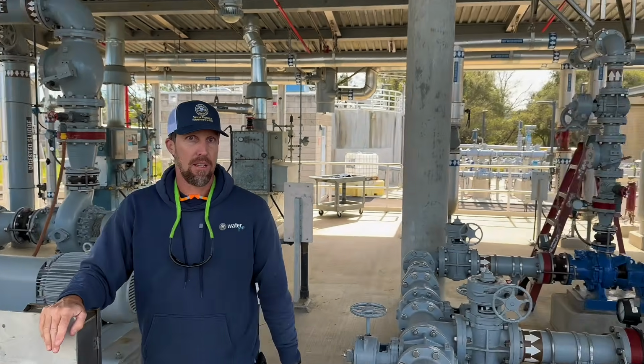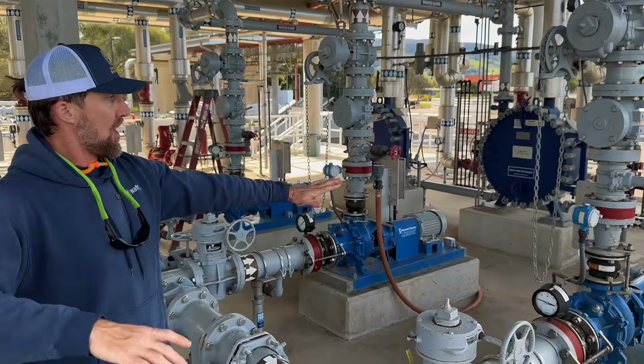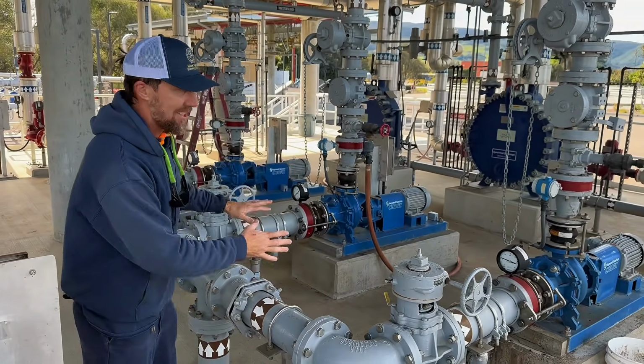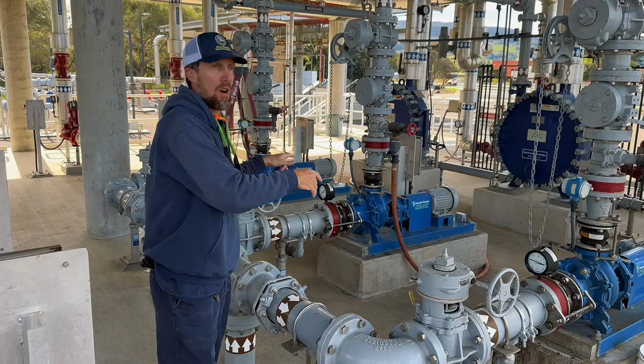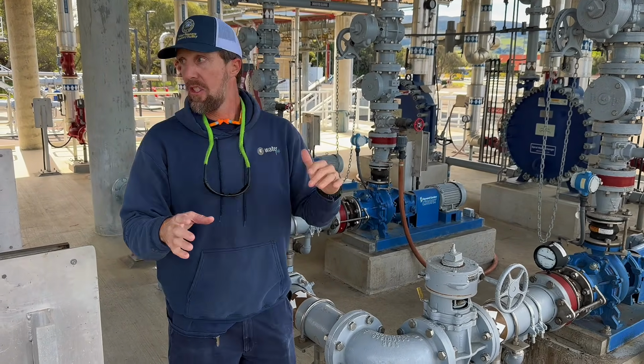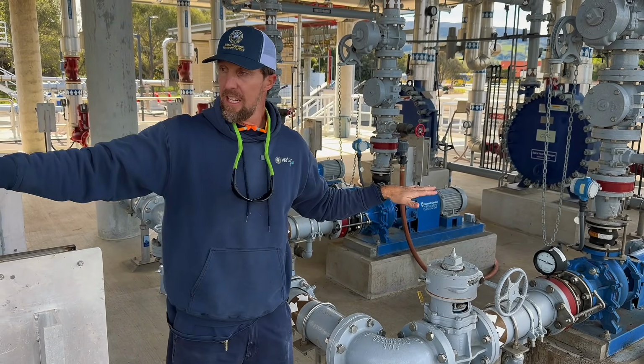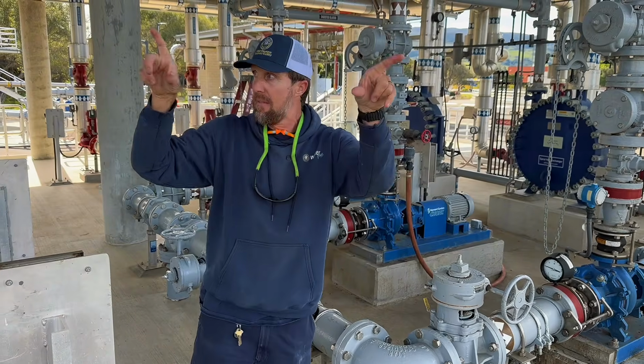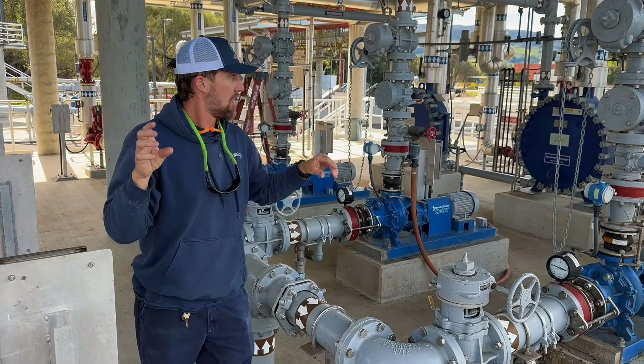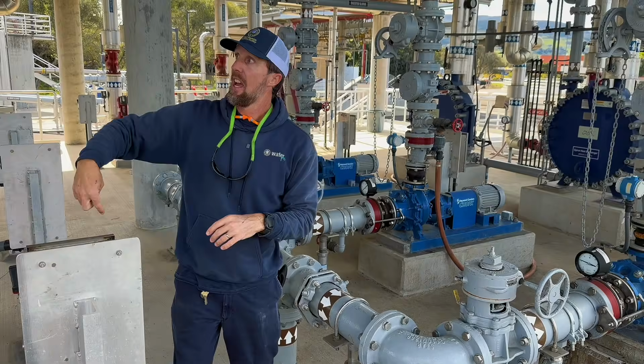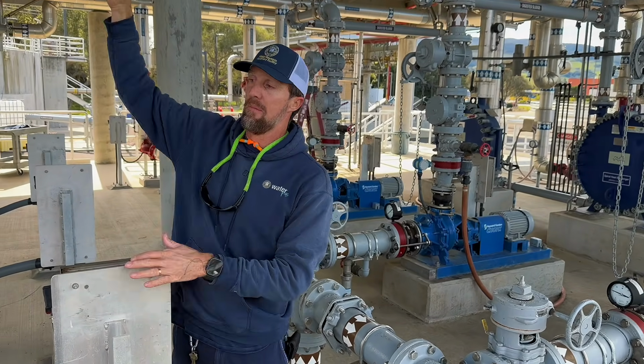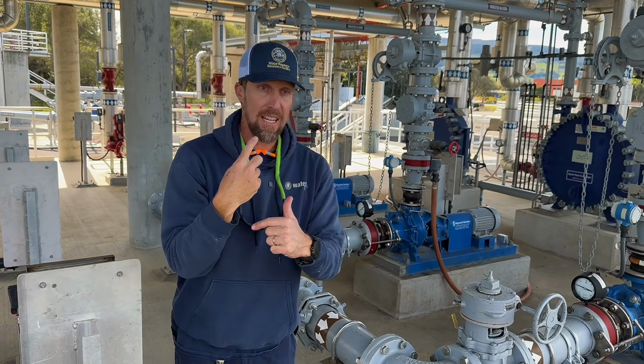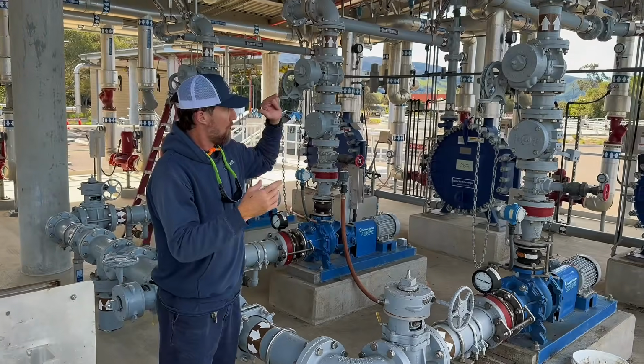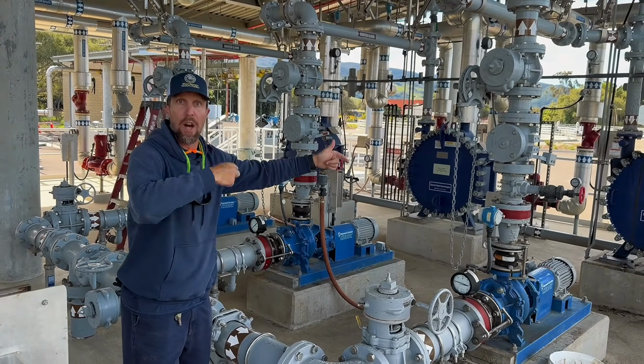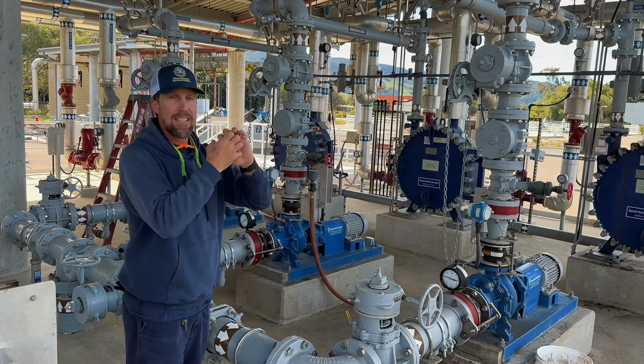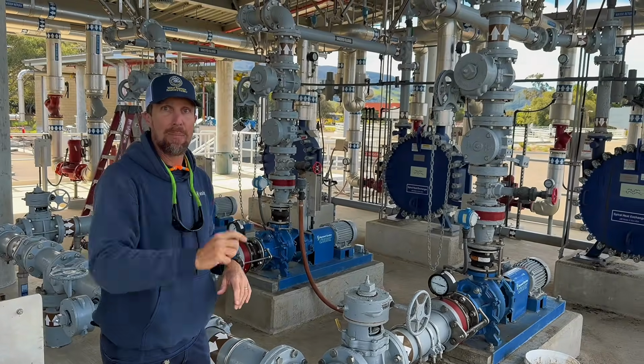Perfect. And what's going on over here? Yeah, so these are the sludge pumps for the heat exchangers. Okay. So just like the solids blend tank, both of these sets of pumps are pulling off the bottom of either digester. In this case, it's up, back in for the mixing. And in this case, it's up through a heat exchanger that has hot water going through it, heat that sludge up to 98 degrees, and back into the tank.